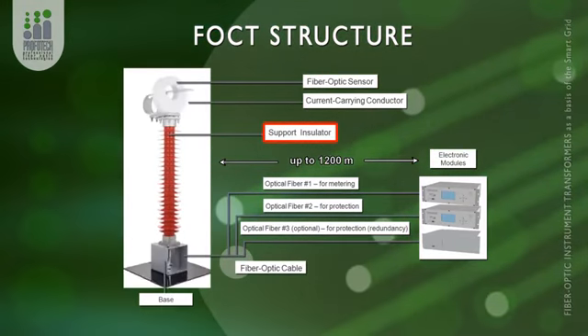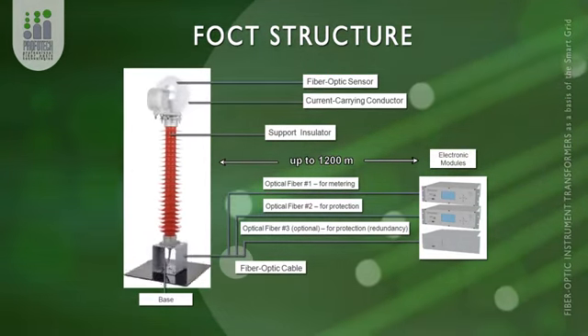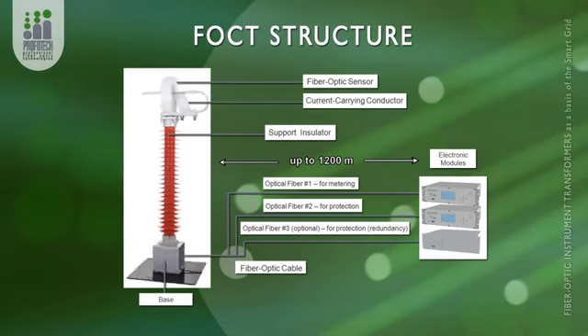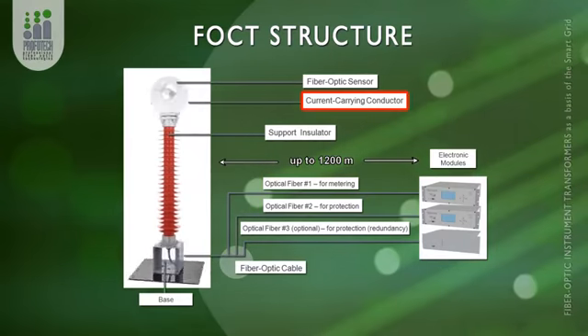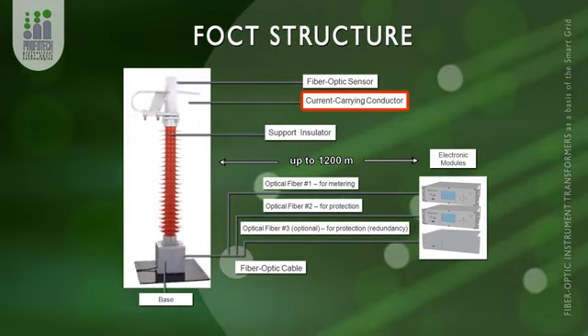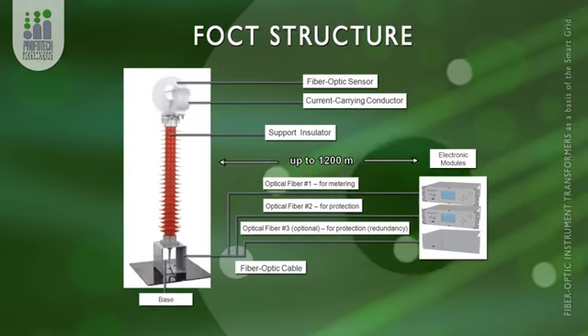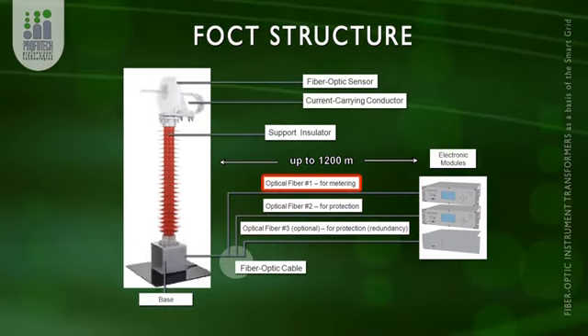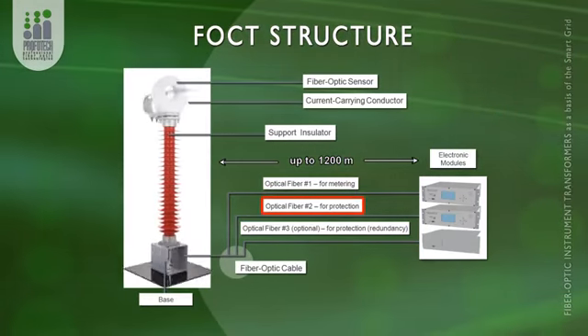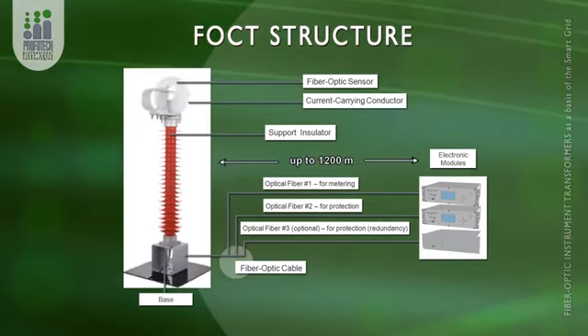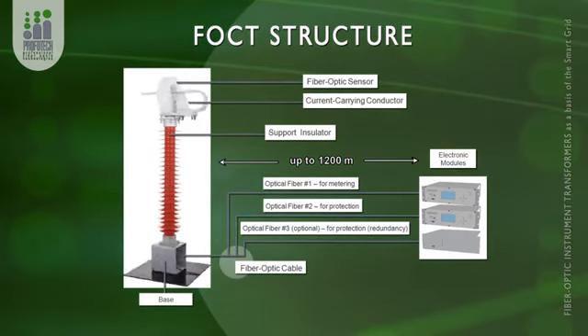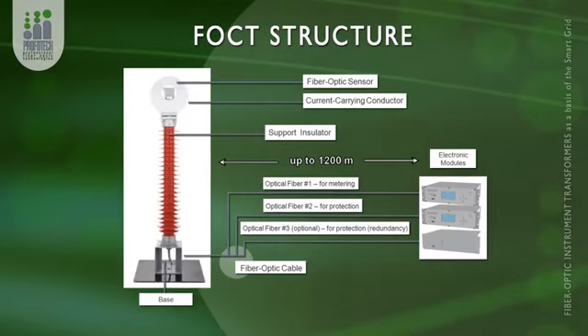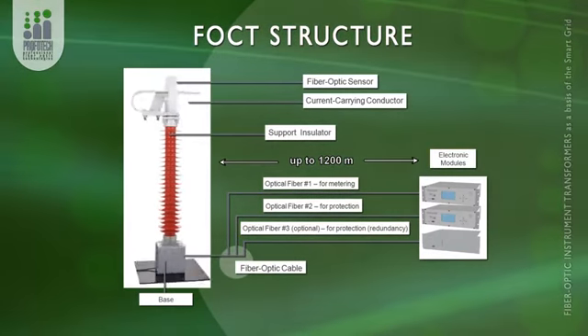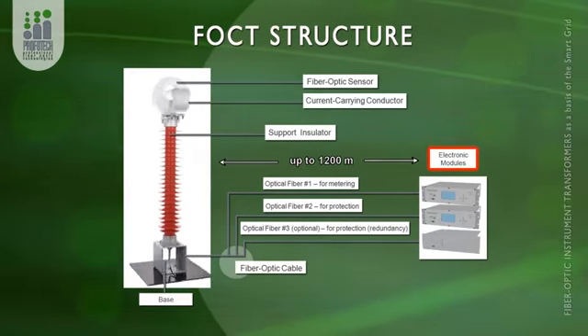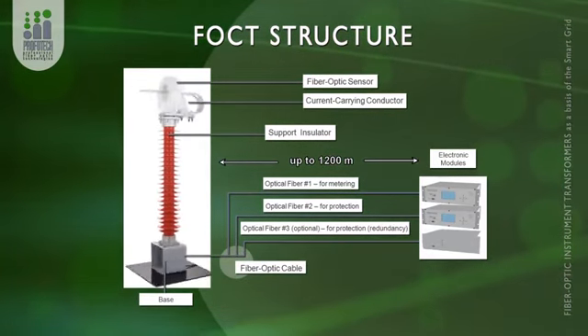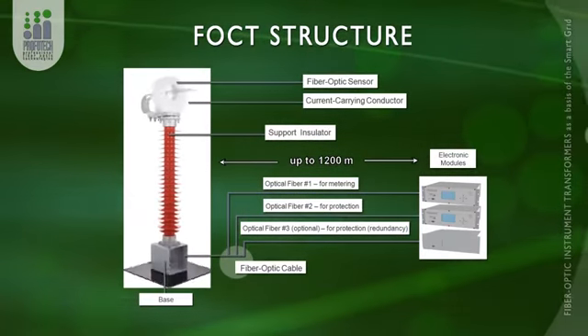We are only using a special optical fiber inside of this sensor. This special fiber is used to sense the current flowing through the current carrying bus. Because of this, we have several options. We can have one optical cable with two optical fibers for metering and for protections, or we can have an additional second cable for redundant protection schemes. These items are installed in the switch yard along with the electronic modules with IEC 61850-9-2 interface. They are installed in the control room of the substation.